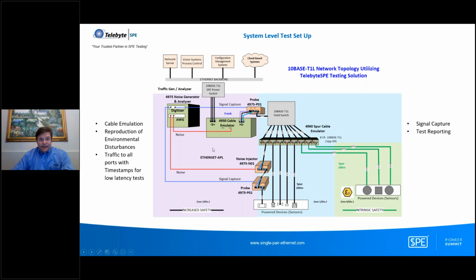Then the last test we're going to talk about is moving to the system level. So we've tested that devices talk from port to port. Now we want to have kind of a system level test just to make sure it's going to work as how it's going to be deployed in the field. And we have a power switch here coming over a trunk. So this power switch is auxiliary powered, and it's providing power over a single pair trunk. We can monitor the signals coming out of that trunk at the end of it.